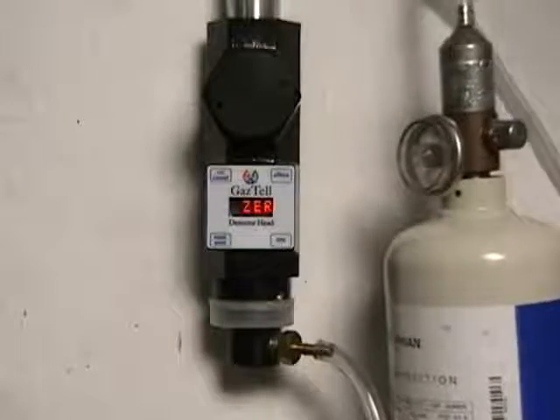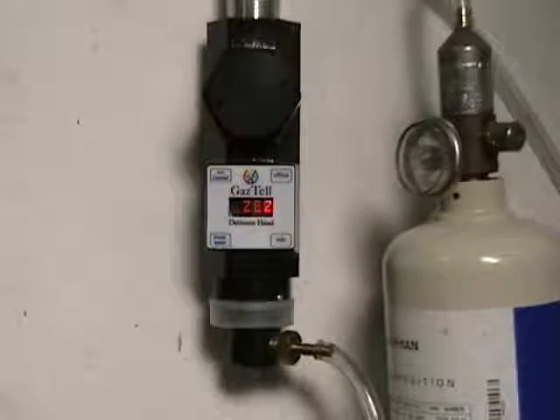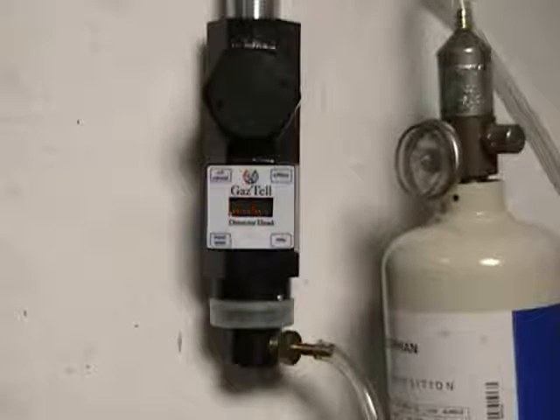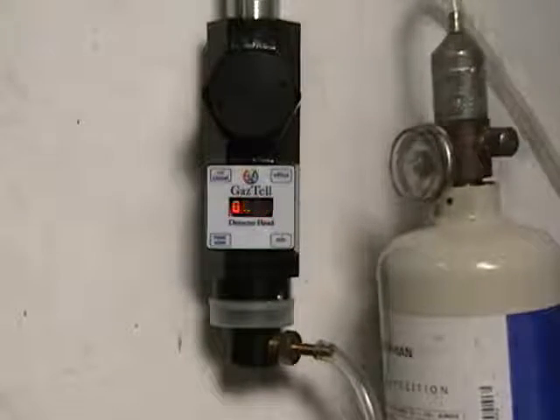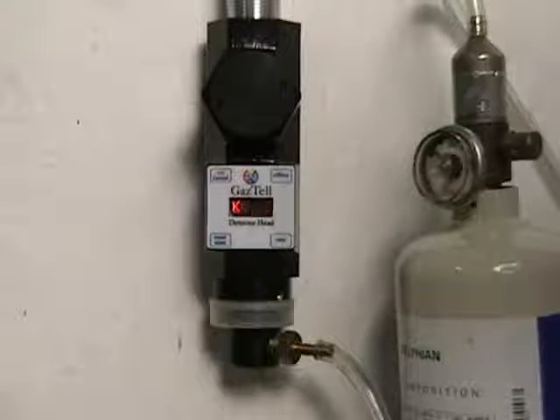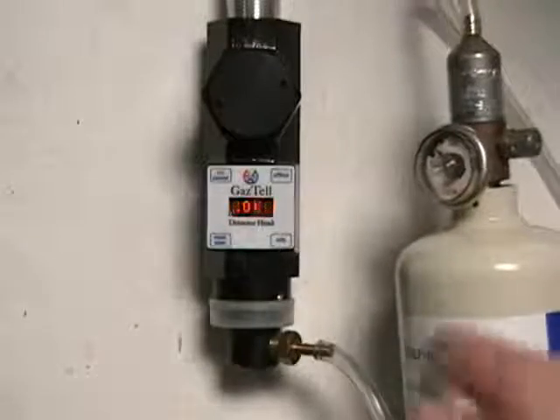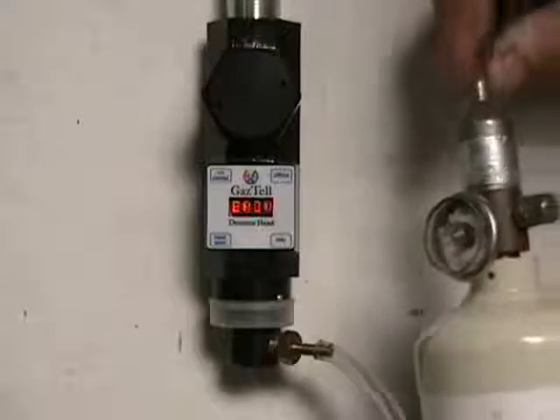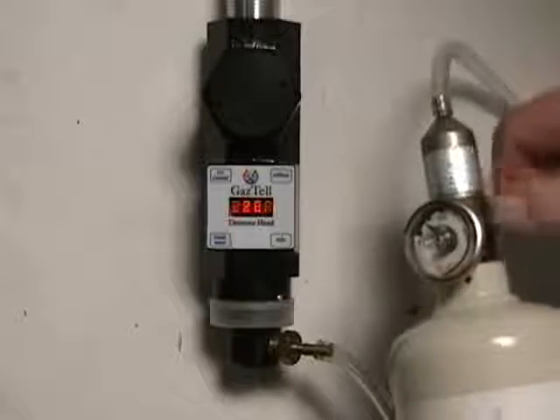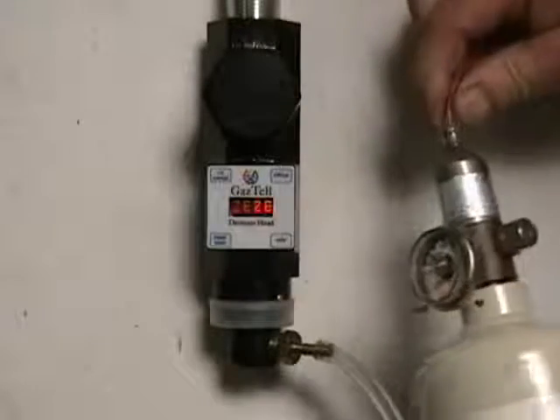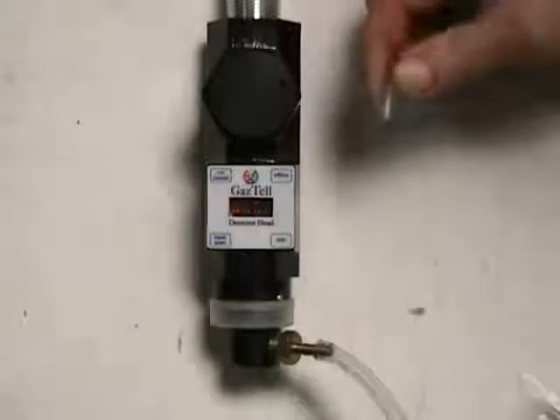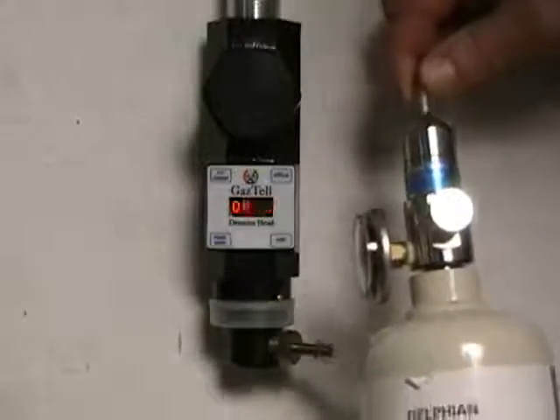If the zero calibration was successful and nothing more is done, the detector will go back online after 120 seconds using the new zero calibration values. This is only true if the detector has been successfully calibrated before. If this is the initial calibration of a new detector head, span calibration must be performed. Make sure you turn off your gas valve.